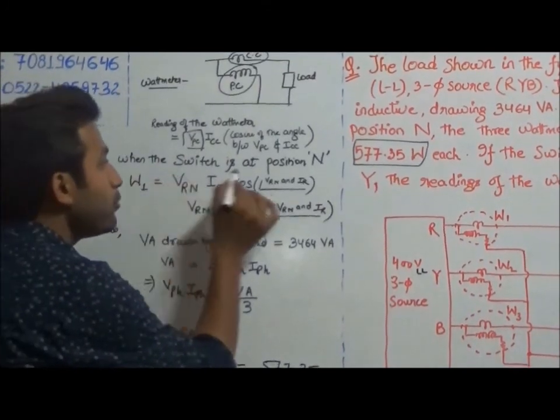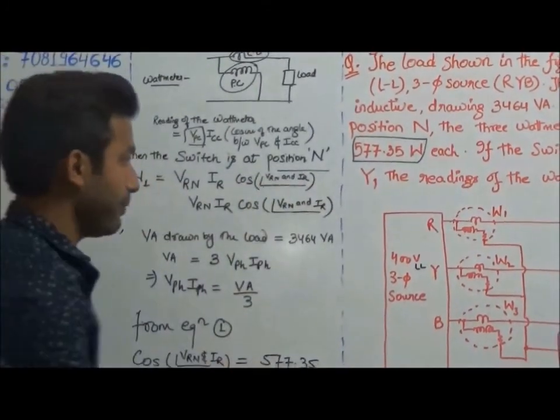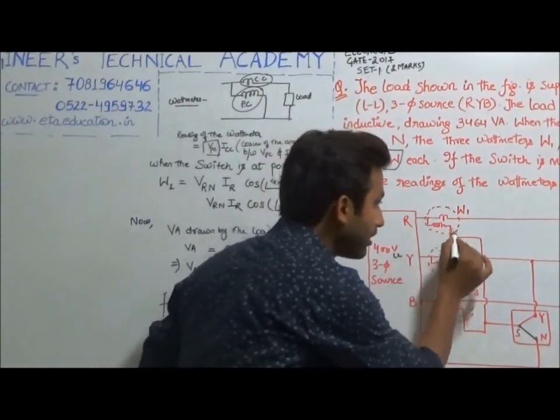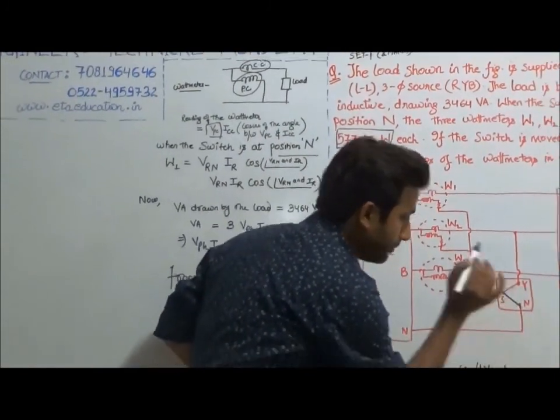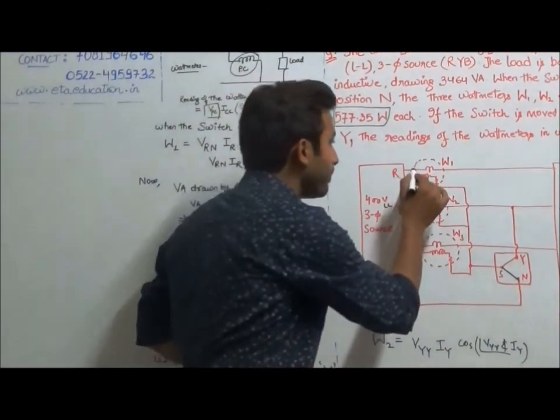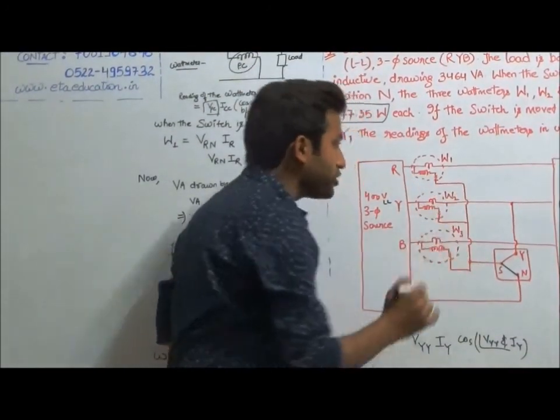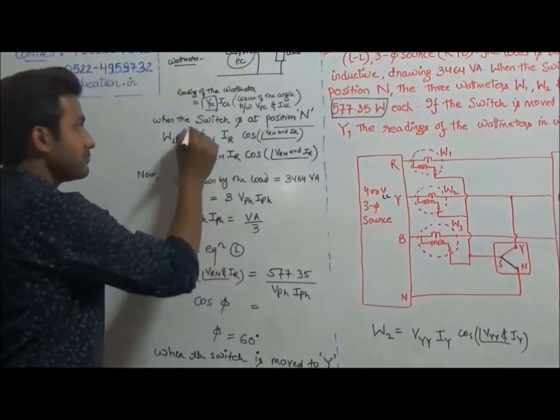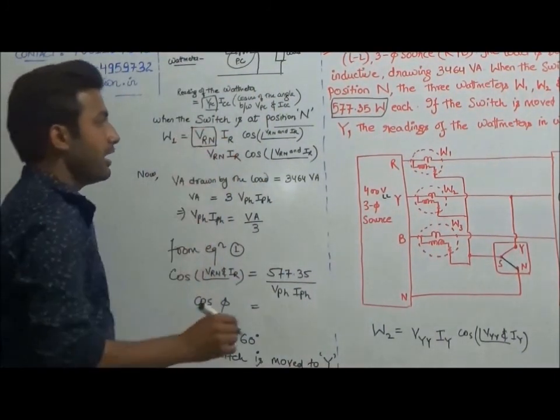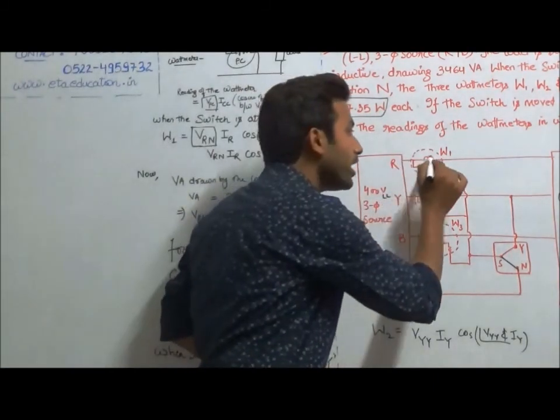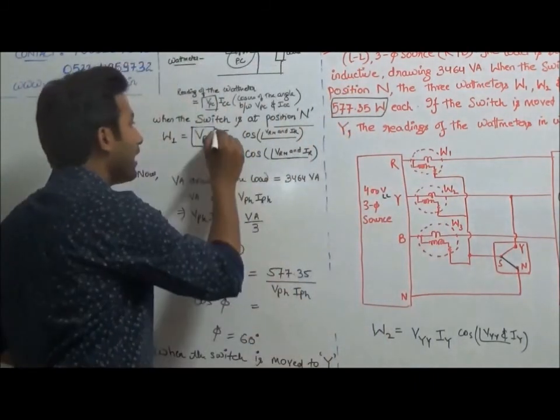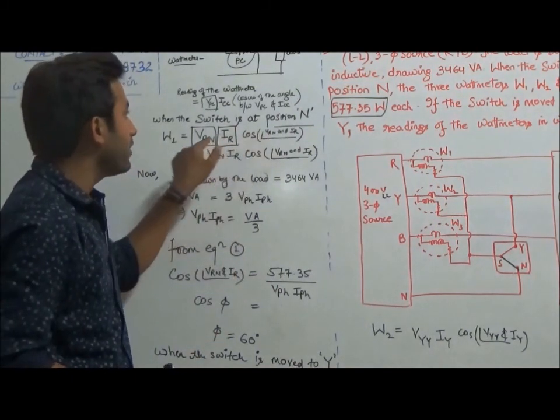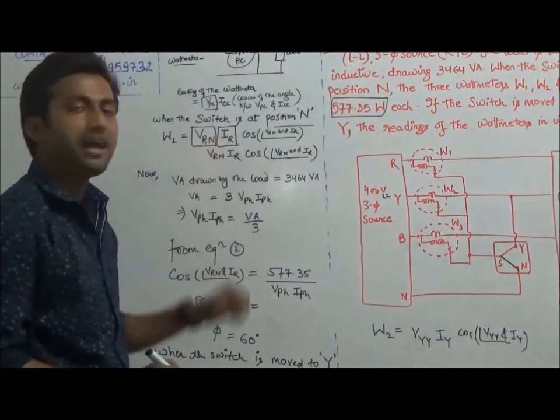When the switch is at position N, the potential coil is connected from R to N. So the voltage across this potential coil is VRN. The current flowing through the current coil is IR, and we need the cosine of the angle between these two quantities, VRN and IR.